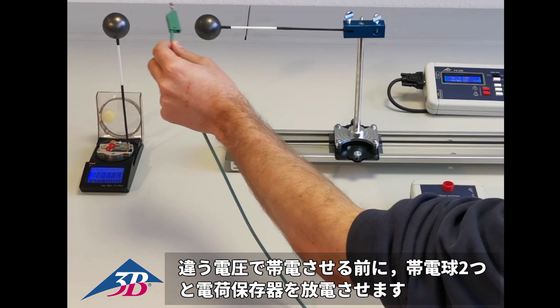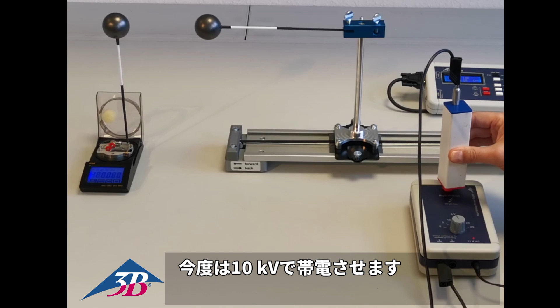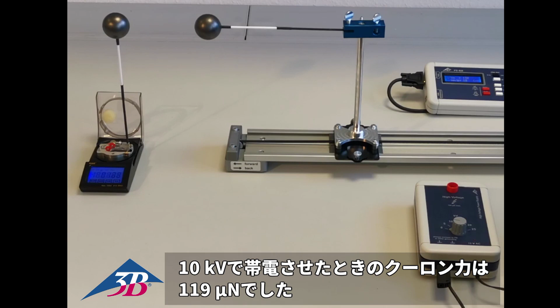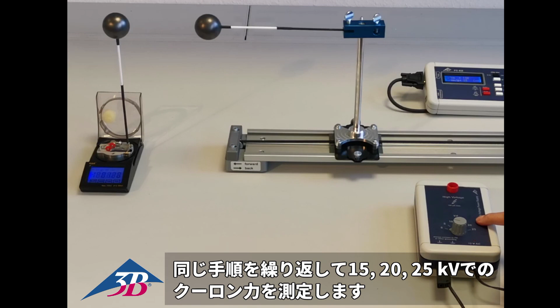Now let's charge spheres with a higher voltage, but before, discharge both spheres with the grounded cable and discharge the capacitor. So we switch to 10 kV. Charge it. Make sure to switch it off as this high voltage power supply is not meant to run permanently. Charge this sphere firstly. Okay, again it's at 0. Charge the capacitor again and charge the second sphere. Now we see if we charge the capacitor with 10 kilovolts, now we have a Coulomb force of 119 micronewton. You repeat this for all kilovolts, 15 kilovolt, 20 kilovolt, 25 kilovolt, and then you have to evaluate your results.